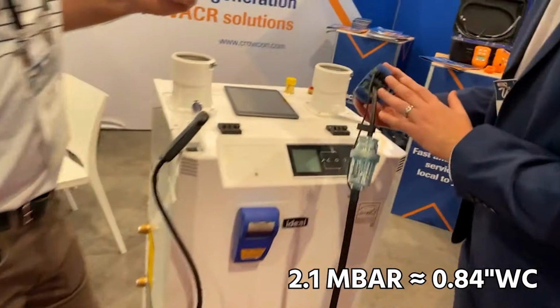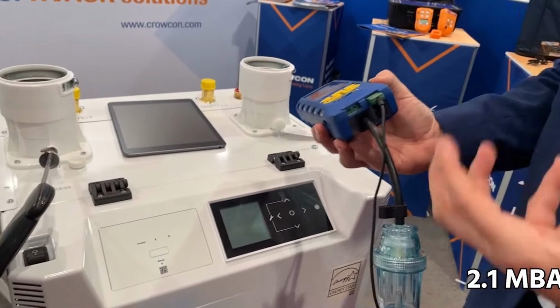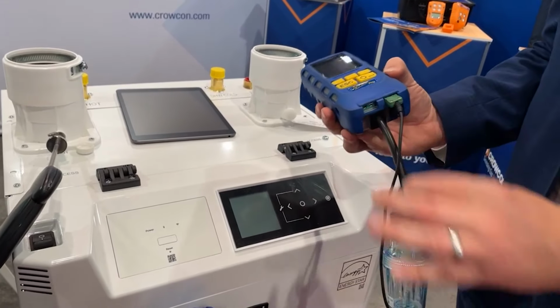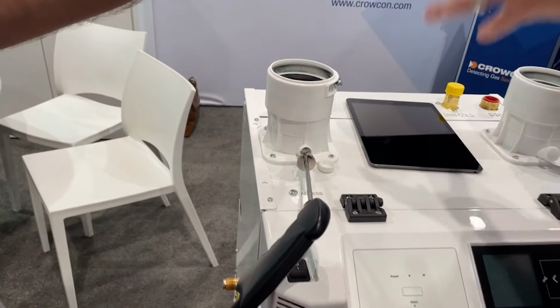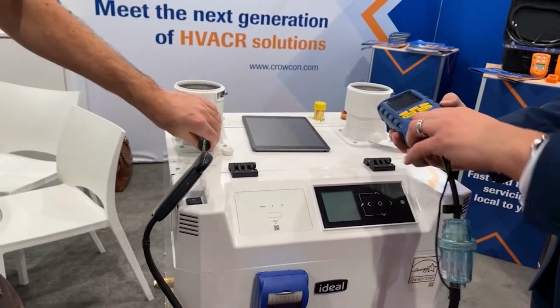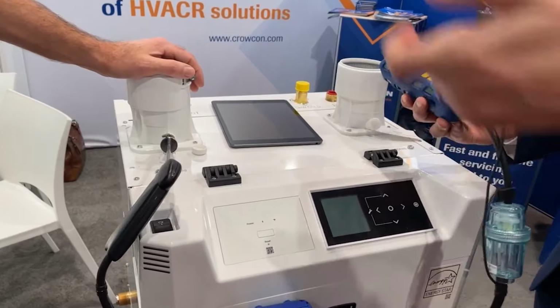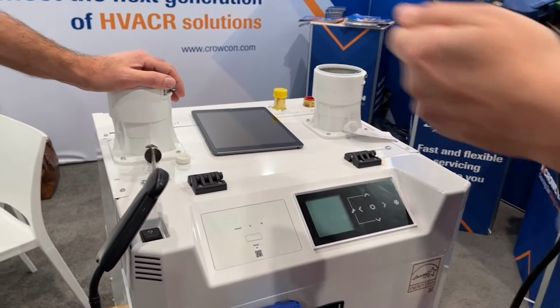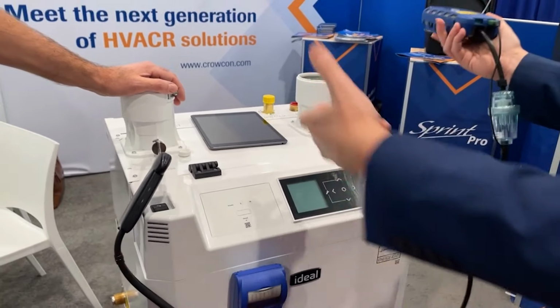So we've got a full suite of pressure measurement there. You've also then got temperature. So you've got the terminals here. This one is connected to the probe, which would give you the temperature of the flue. But also you can use these and connect different clamps and probes to do differential temperature measurement. You could clamp it on a flow and return pipe or something and see the differences there.